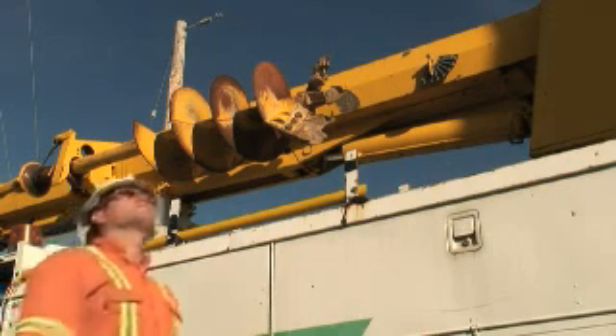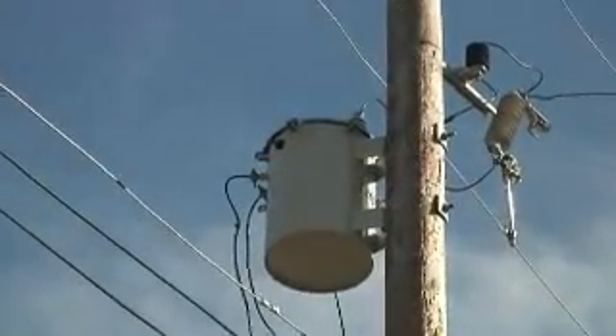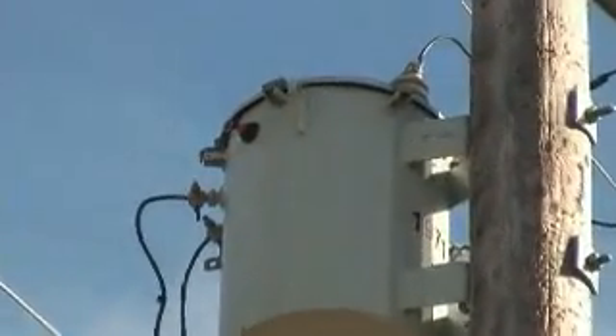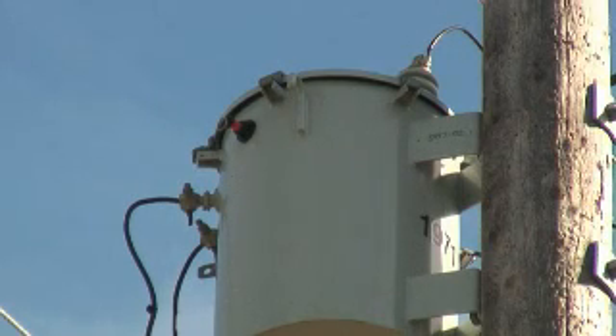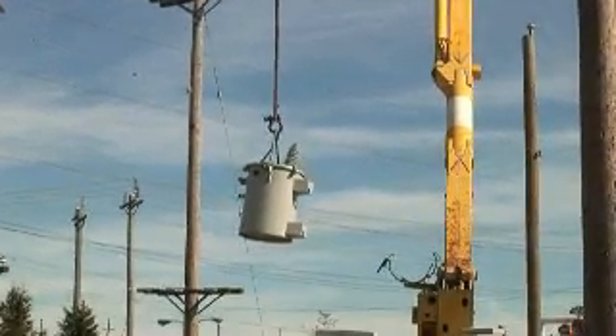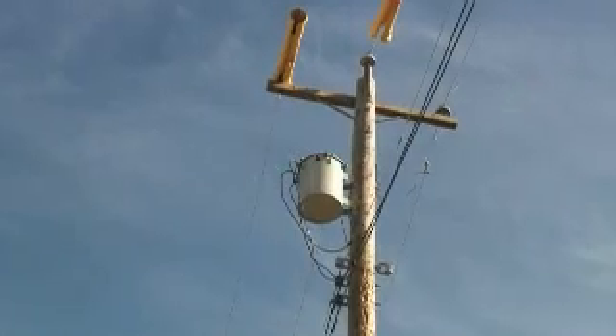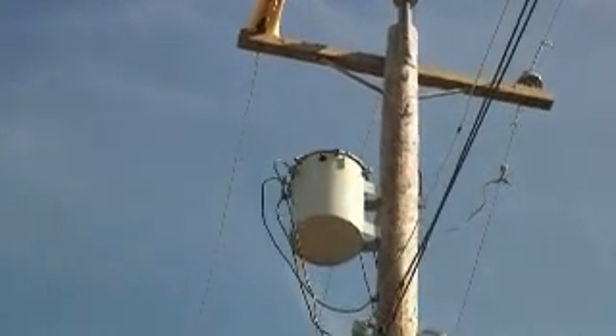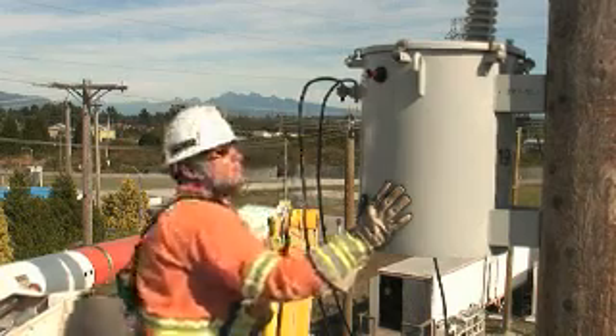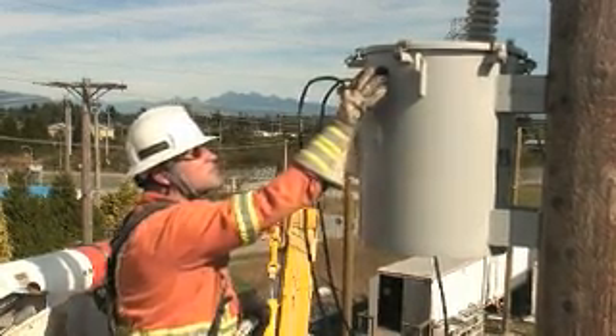By simply looking up, the line worker can see that the transformer has an internal fault and must not be re-energized. An IFD-equipped transformer with the highly visible flag displayed must be taken out of service and replaced. The flag has been designed for easy identification in daylight and in the dark with a flashlight. Note that the orange indicator flag cannot be reset.